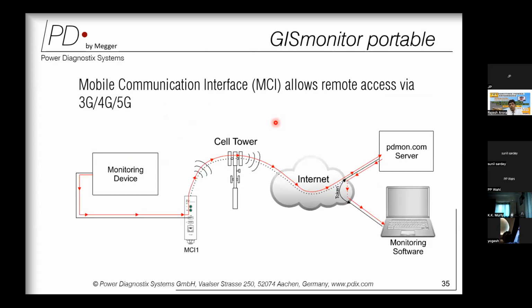Moving forward, this portable device can be connected with a mobile communication interface card, and this allows you to access or monitor the partial discharge instrument through a cell phone via internet from any remote location. So if you are in one location or in your office, and the instrument is in, say, an XYZ substation, still if it is equipped with the mobile communication interface, you can access the data and monitor everything as if you are in front of the instrument.